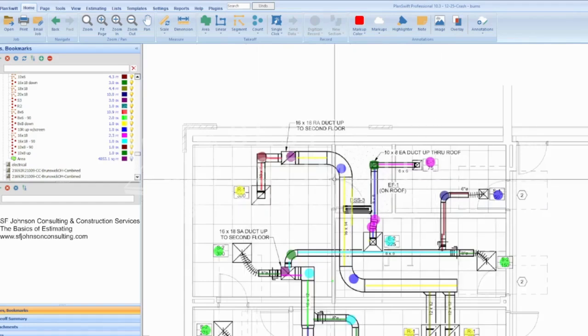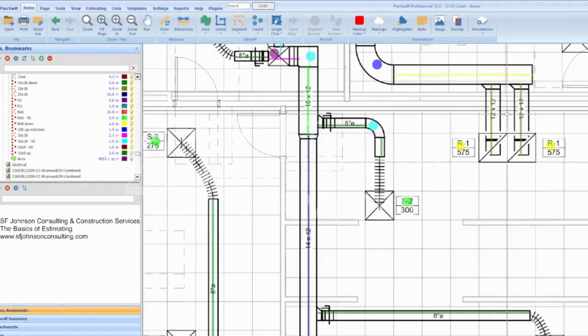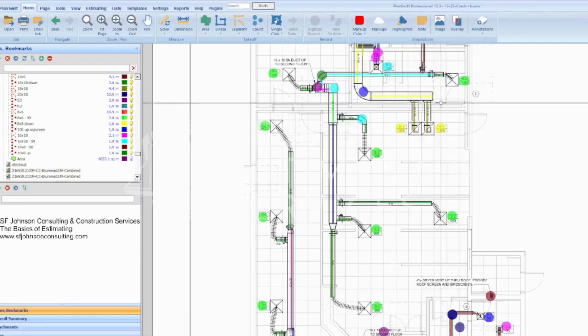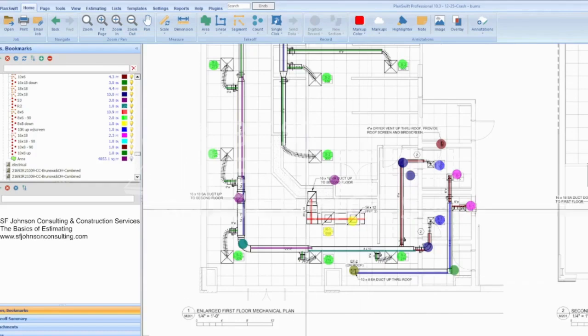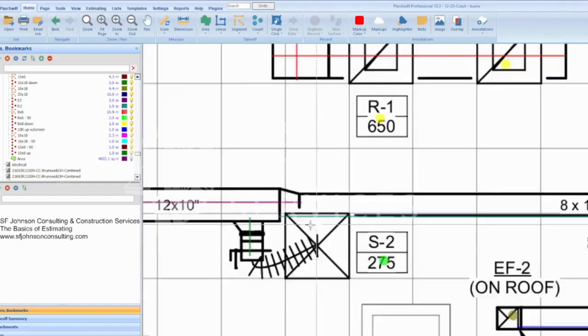So when you're doing the takeoff for an HVAC, you have your equipment given to you on the equipment schedule. You don't have to ever worry about that. But then you go into all of the ductwork. You measure the spiral ductwork as opposed to the rectangular ductwork, and then your 90 degrees and 45-degree angles, then all of your grills, return grills, supply grills are always next to the equipment, and all of your 90 degrees, and then all of your supply grills usually come with the damper, and that's the symbol for damper.